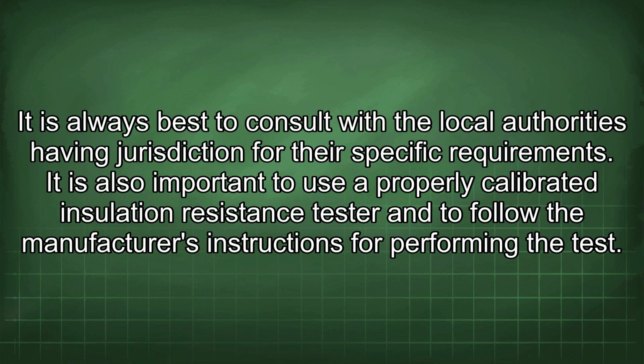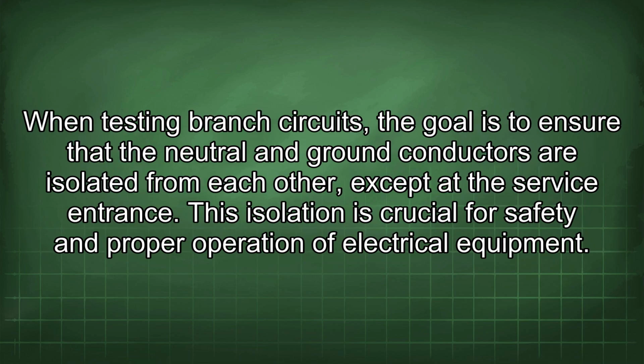It is also important to use a properly calibrated insulation resistance tester and to follow the manufacturer's instructions for performing the test. When testing branch circuits, the goal is to ensure that the neutral and ground conductors are isolated from each other except at the service entrance. This isolation is crucial for safety and proper operation of electrical equipment.